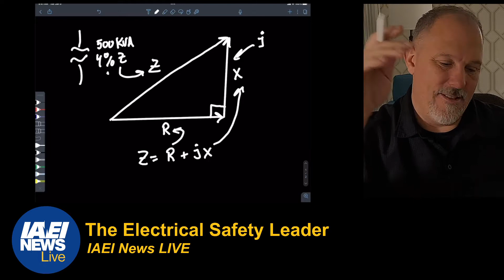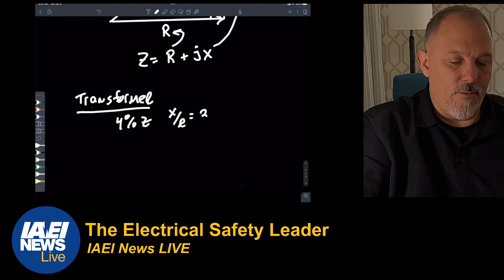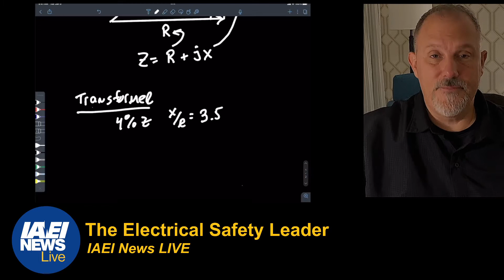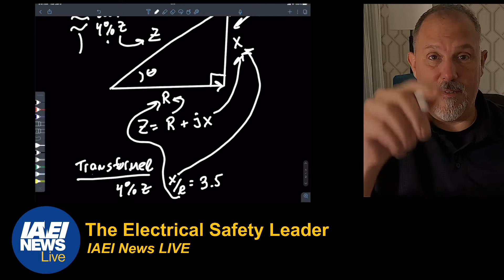transformers will tell you, say we're dealing with a transformer, that it's 4% Z with an X to R ratio of, say, 3.5. What does that mean? There's your X, and there's your R. What they're giving you is the angle — they're giving you everything you need to calculate this angle theta, which is your power factor. By giving you the percent impedance and the X to R ratio, they're giving you enough to calculate R and X of that product.